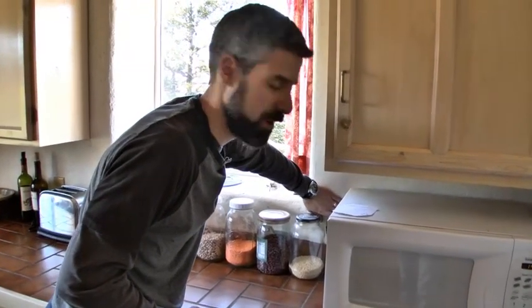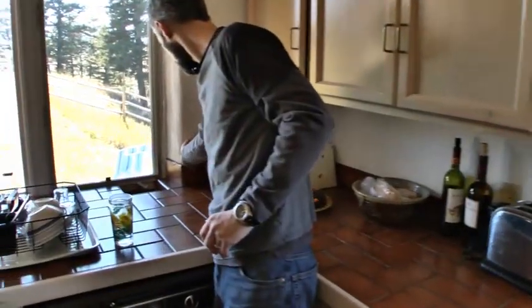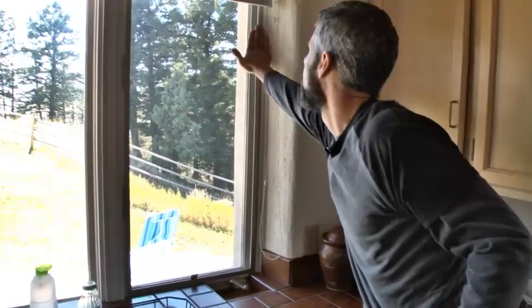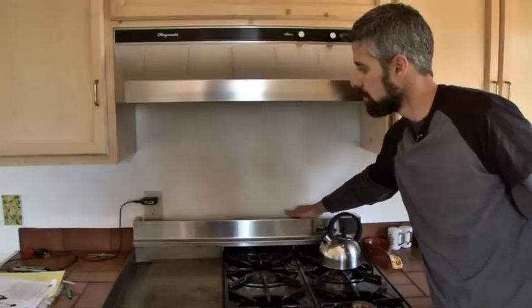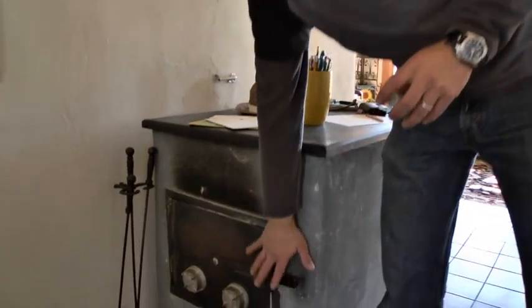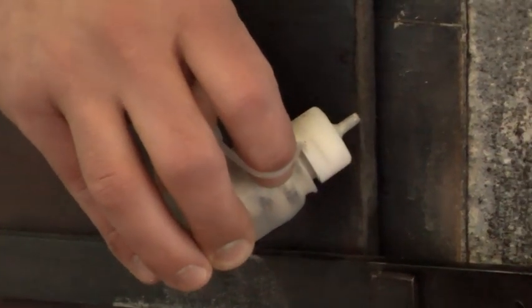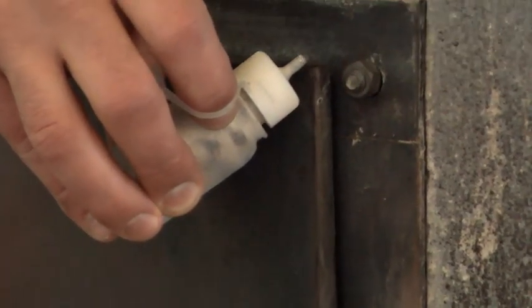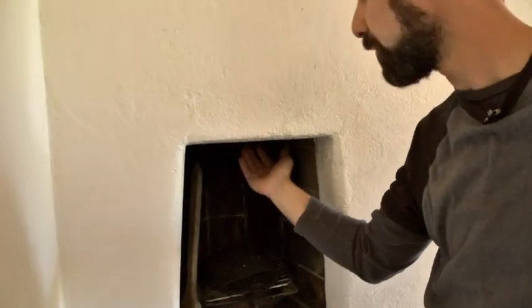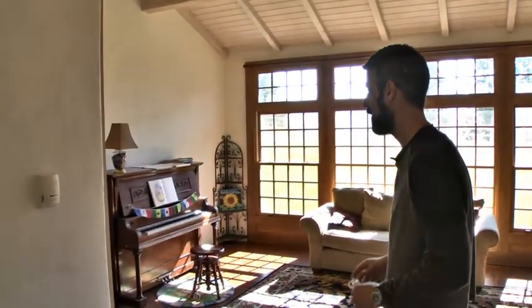I'm actually feeling quite a bit of leaking out of some of these outlets here — this one has a good bit coming out. I'm feeling around at the windows here. I can already feel a pretty good amount of air, and you can see that smoke just blowing through there. I'm also feeling air coming in through this flue — here's the penetration for the flue coming out of this wood burning stove. I do feel a good bit of air coming out of there, so that's accounting for some of this air loss we're seeing.